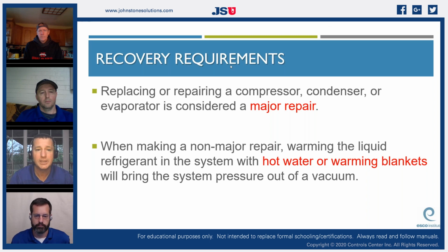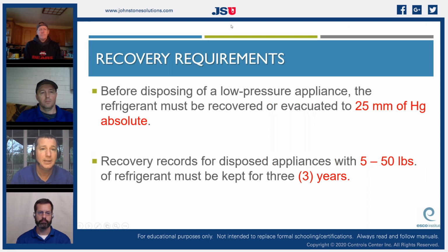Replacing or repairing a compressor, condenser, or evaporator is considered a major repair, just like it is in every other category. So when making a non-major repair, warming the liquid refrigerant in the system with hot water or warming blankets will bring the system pressure out of vacuum. All it does is warm it up just enough to get it a couple PSI positive. So before disposing of a low pressure appliance, the refrigerant must be recovered and evacuated to 25 millimeters of mercury. So it's pretty low. That's because we have to make sure we get all that refrigerant out of there.